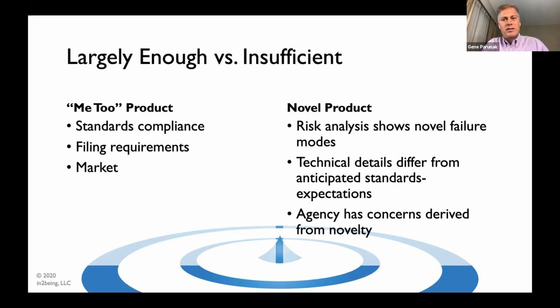You can think of standards as a way to reduce the number of questions a regulator is going to need to ask you about your device. For example, if a device has electronics in it, the IEC 60601 family of standards will go a long way toward reducing the number of questions a regulator has to ask. A standard like 14971 gives us a uniform framework to talk about risk, but that doesn't mean all of our risks get solved the minute we read the standard. It does help us get on the same page to address what risks emerge and what risks are important.